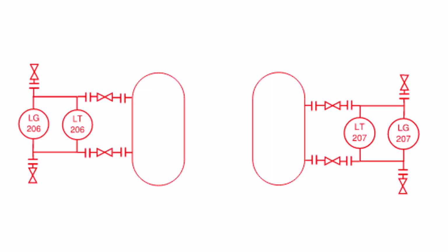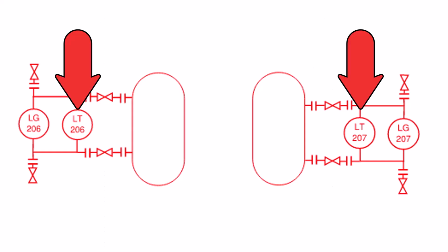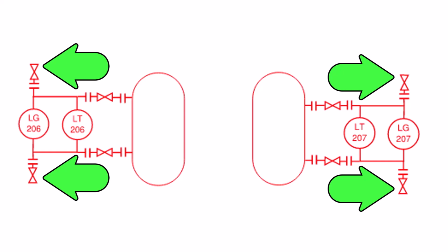When complete, our new setup will look like this, with isolation valves on the top and bottom leg, coming off the sour oil traps. Then the guided wave radar column, and then the Magtech local level gauge, with a top bleed and a bottom bleed.